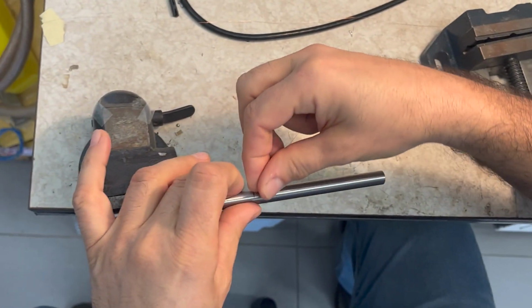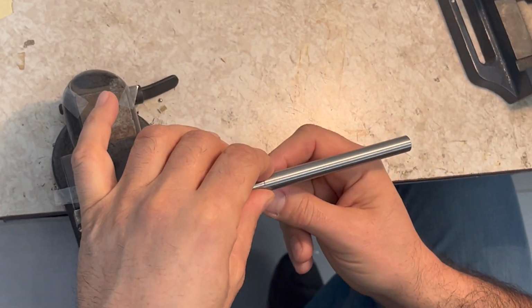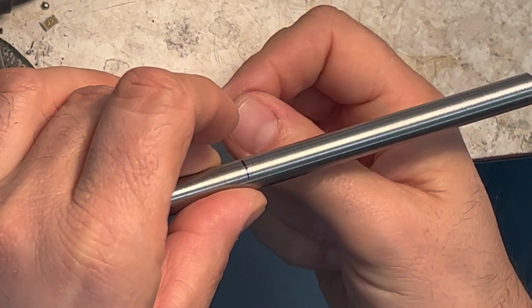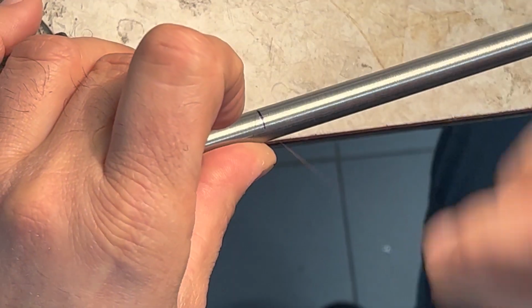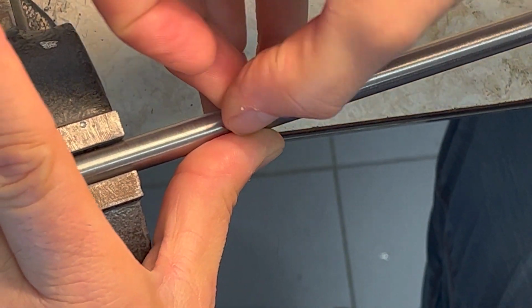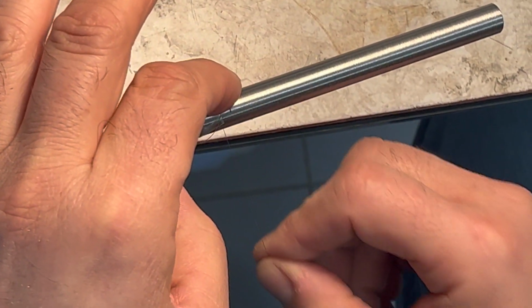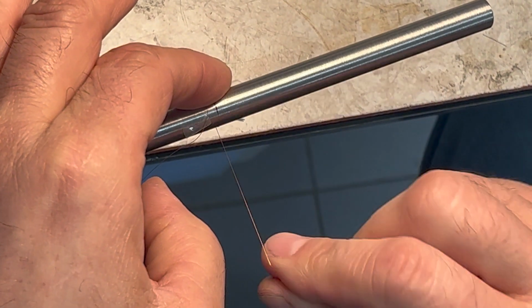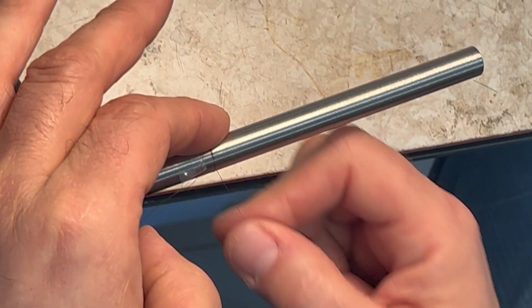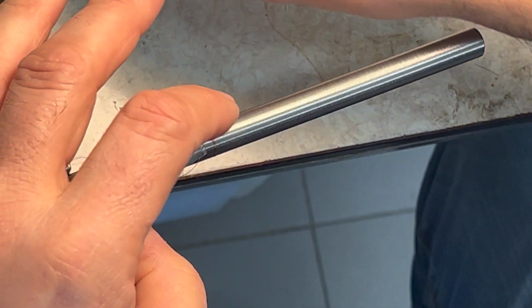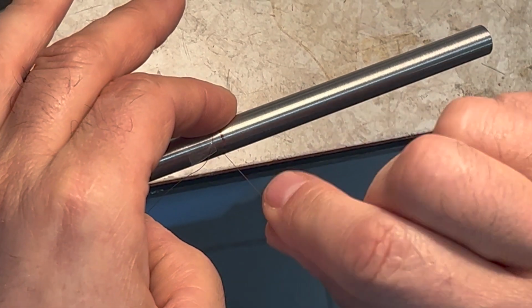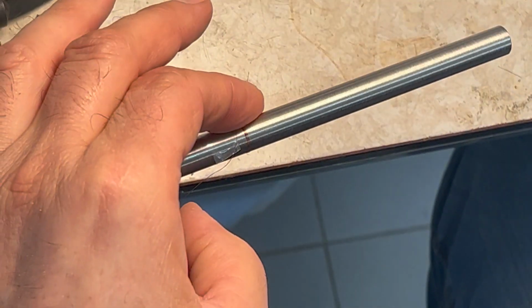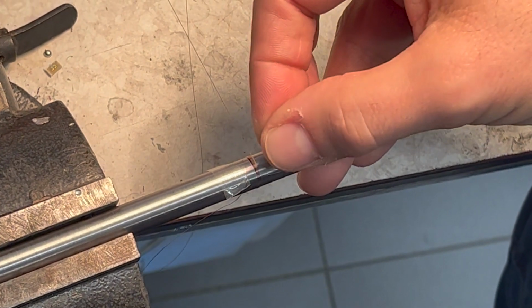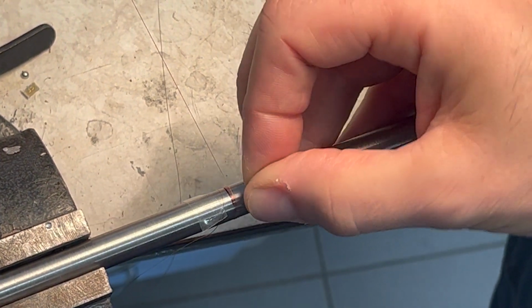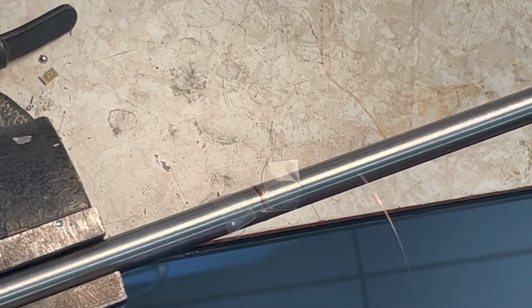The pickup coil is realized with a very thin insulated copper wire. In our case, its nominal diameter is 0.05 millimeters, but after measurement with the gauge, it turns out to be 0.06. It is important to know the diameter of the wire with which you prepare the coil, because the actual cross-section of the coil will be the cross-section of the sample plus the thickness of the wire. This means that the pickup coil will pick not only the signal coming from the sample, but also from the thin layer of air surrounding the sample due to the thickness of the wire. It is therefore needed to know the correct diameter of the wire in order to be able to compensate for this contribution of air.